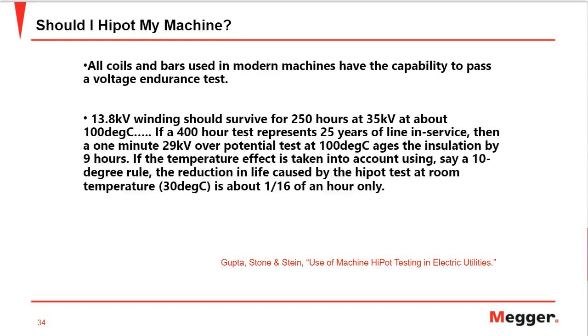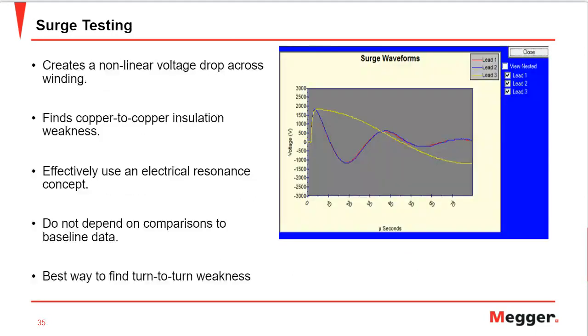So that was on the hipot testing. We'll move ahead with our next testing, which is the surge testing. Coming back to turn fault, which comprises the majority of faults, as we discussed, surge testing is the only testing which can help us find turn faults, and those are the major faults. And it's one of the tests which effectively uses the electrical resonance concept. We'll see in the upcoming slides how that concept is being used.